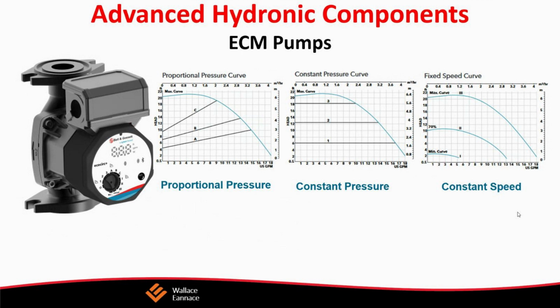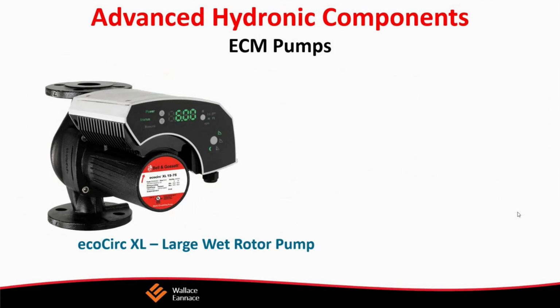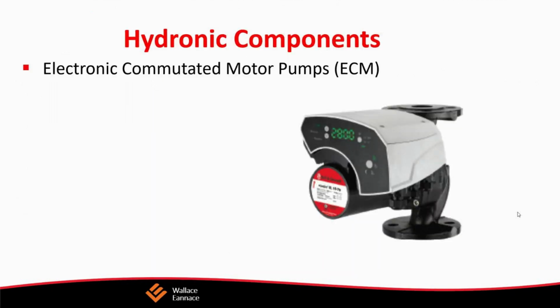And that is something that's going to become more sophisticated with time. As time goes on, Bell & Gossett will be integrating Circ Guard and other components to allow the pump to adjust to the external variables of the system. But right now, it also assists in air elimination, because it has an automatic air purge to remove any trapped air in the pump. It has one turn knob and a multicolor LED display for easy reading, and also for setting up the pump.